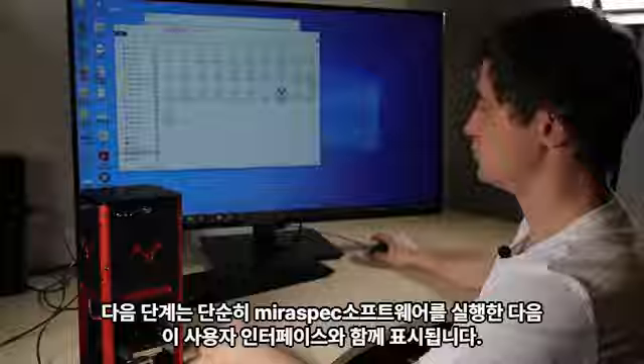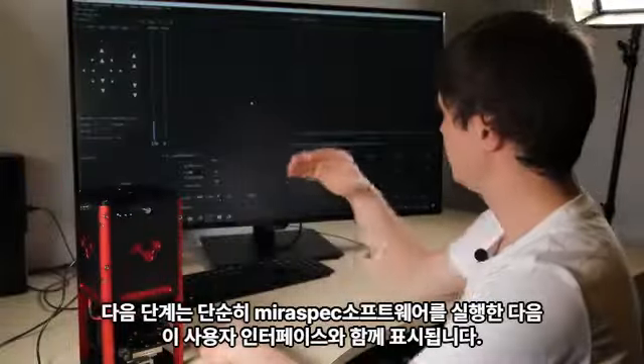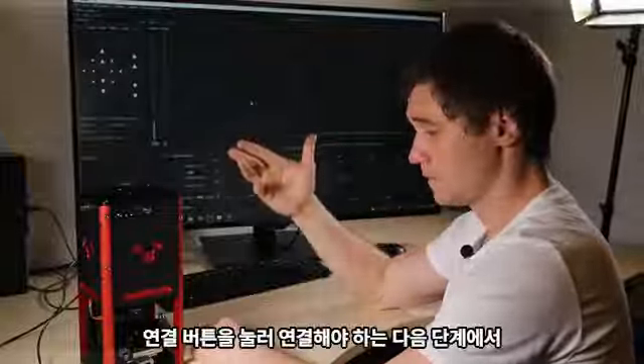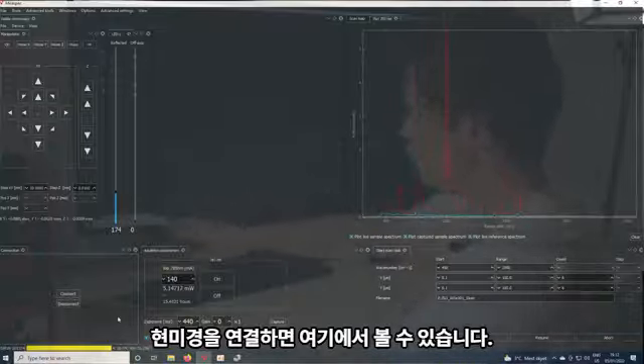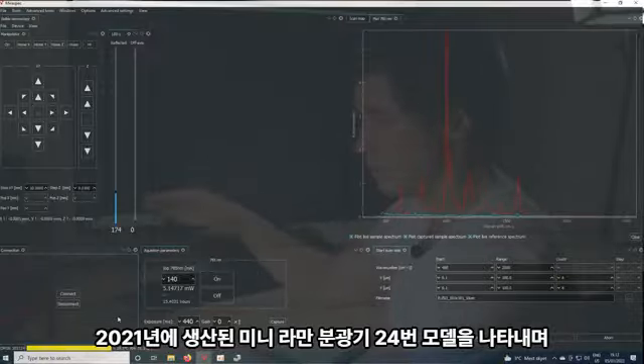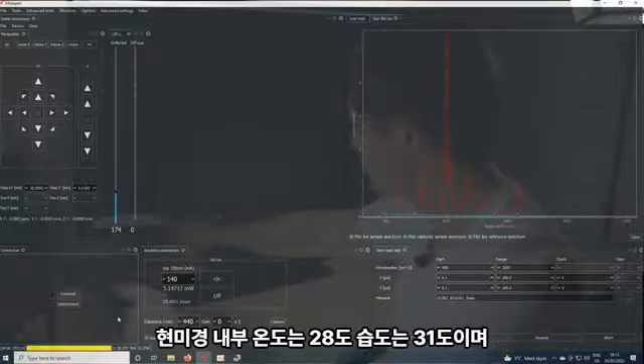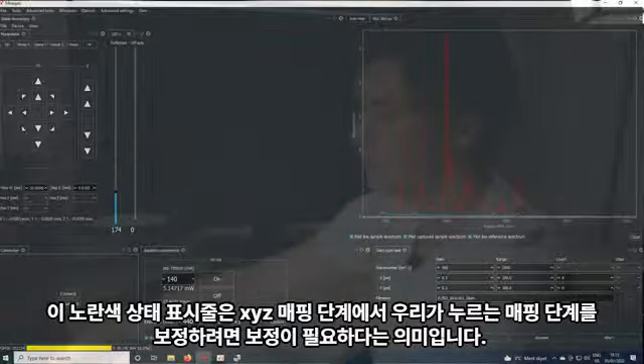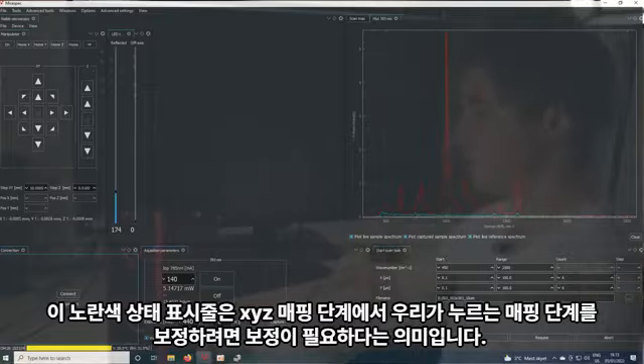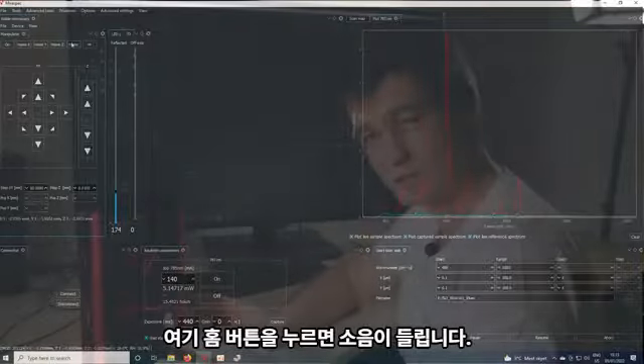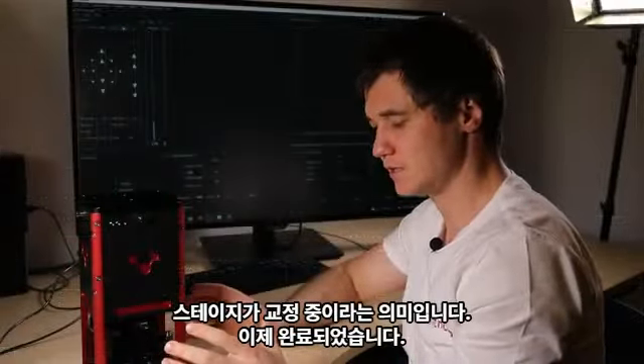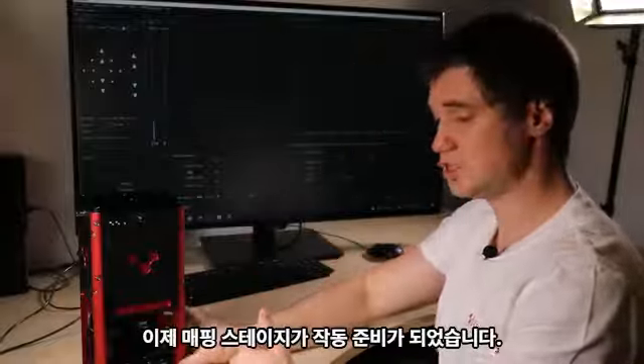The next step, simply run miraspec software, and it will appear with this user interface. The next step, we should connect by pressing the connect button. We connect the microscope, and you can see here an indication of the model of the miniRaman spectrometer, number 24, produced in 2021. The temperature inside the microscope is 28 degrees, humidity is 31, and this yellow status bar means that the XYZ mapping stage requires calibration. In order to calibrate the mapping stage, we press the home button here, and you hear the noise, which means that the stage is under calibration. It's done now. Now the mapping stage is ready for operation.